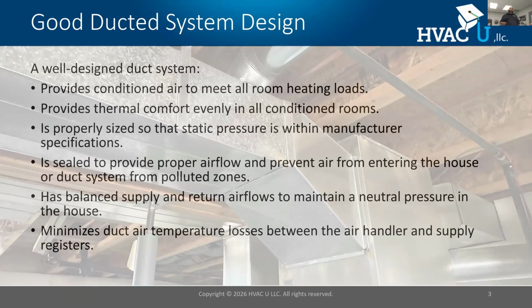All right. If you look at Manual J, it says a good ducted design should keep the rooms within less than 3 degrees Fahrenheit. All right, so we want them to be thermally even. All right, we want those rooms to be comfortable. Brett mentioned static pressure. We need to make sure that our static pressure is modest and within specifications. We also want to make sure the ducts are sealed.